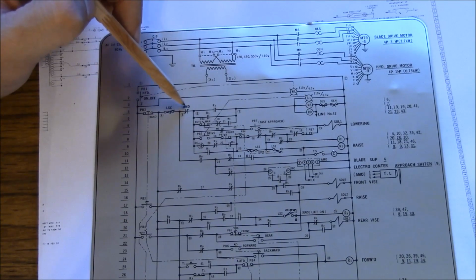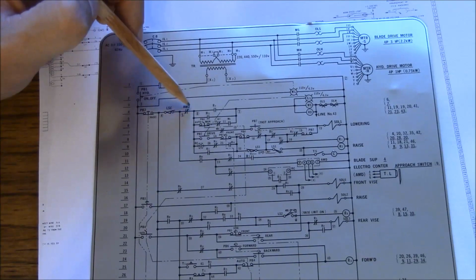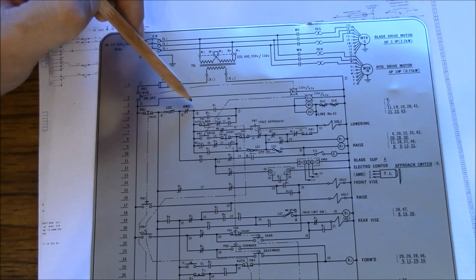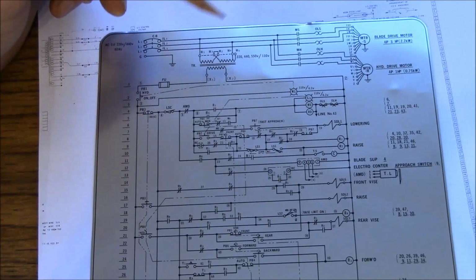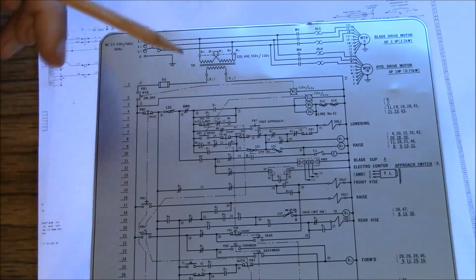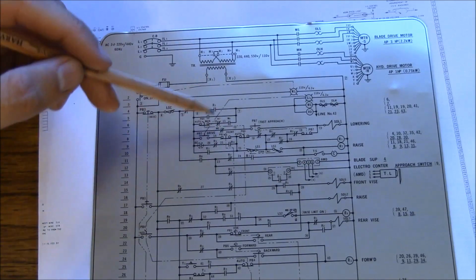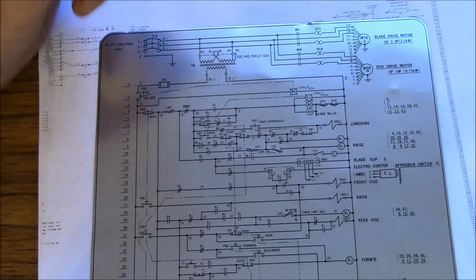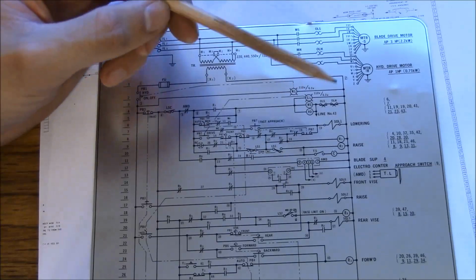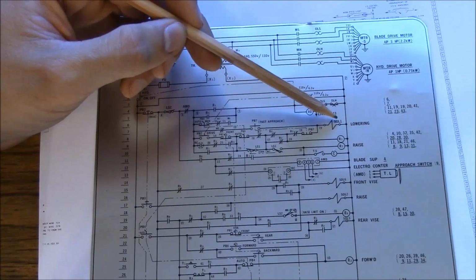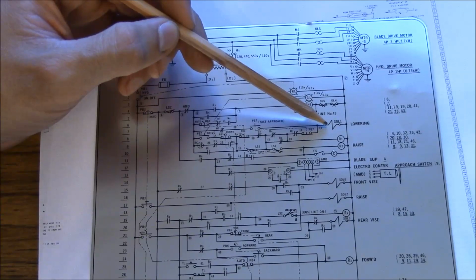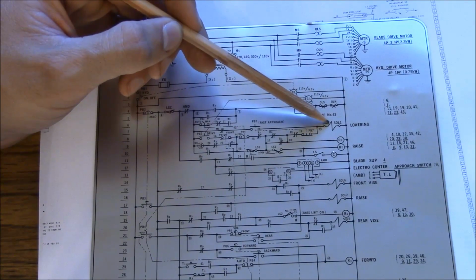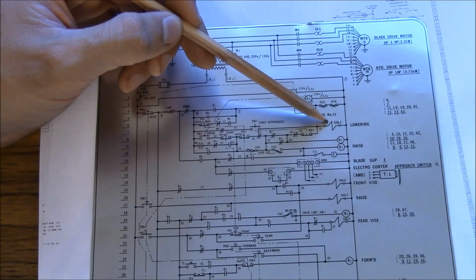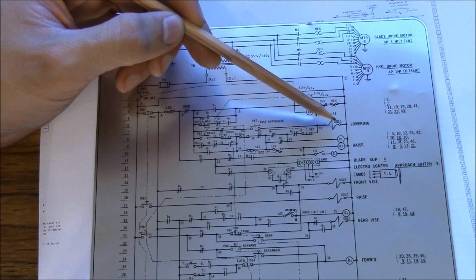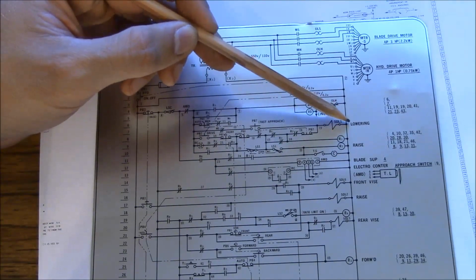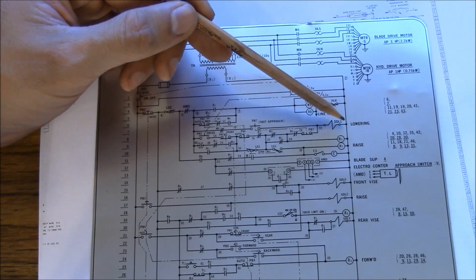Or this AMD relay opens. That's probably some kind of a safety relay. So that would kill power to it as well. So that's basically how any of these circuits will work. So you can look, there's more symbols here that are relevant. So this kind of squiggly line right here, SOL1, that's a solenoid. So probably that's a hydraulic solenoid, meaning it's an electric coil that actuates a valve. And you see it says lowering right here, so that's probably for lowering the blade.